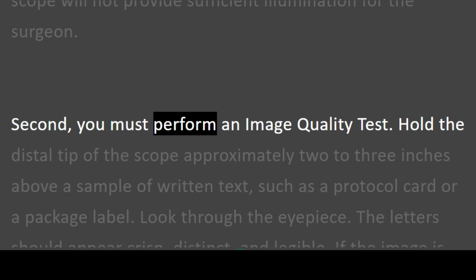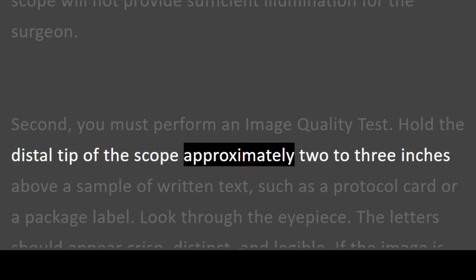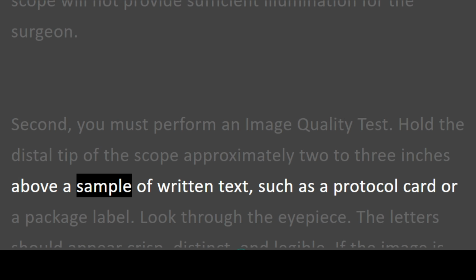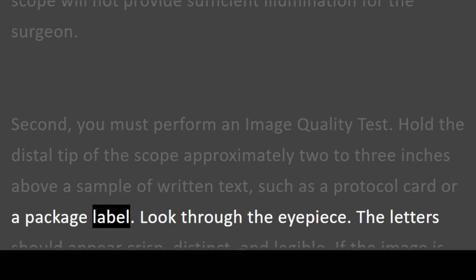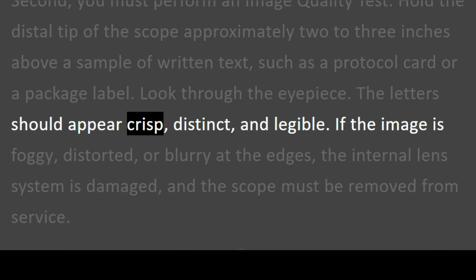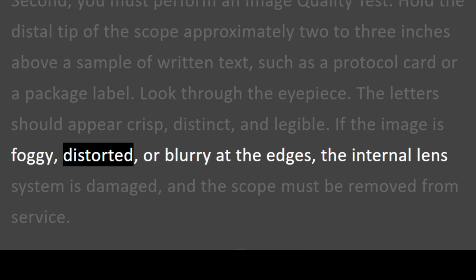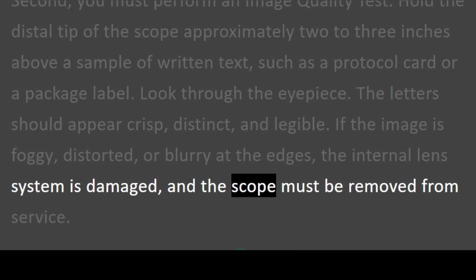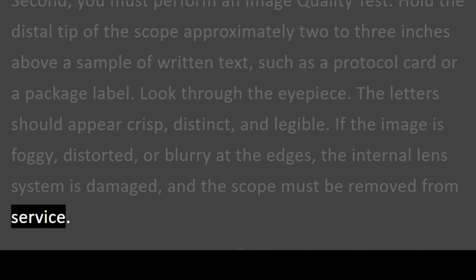Second, you must perform an image quality test. Hold the distal tip of the scope approximately 2 to 3 inches above a sample of written text, such as a protocol card or a package label. Look through the eyepiece. The letters should appear crisp, distinct, and legible. If the image is foggy, distorted, or blurry at the edges, the internal lens system is damaged, and the scope must be removed from service.